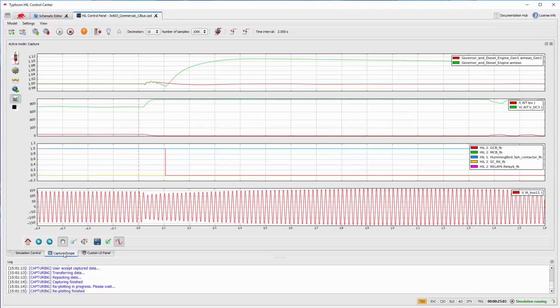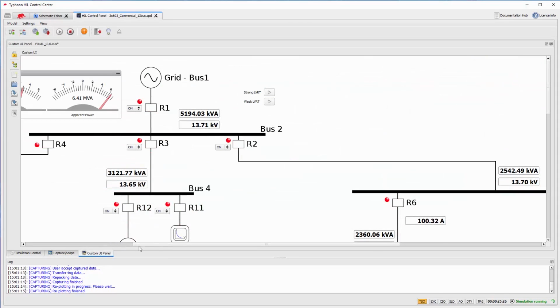As we can see, only the Woodward controlled genset disconnected from the grid. The AIT inverter stopped its operation for 1.30 seconds during the time when the grid voltage was below 90% of its nominal value. When the voltage level reached 90%, the AIT started operating, but with similar behavior to what was seen in the last short circuit case.